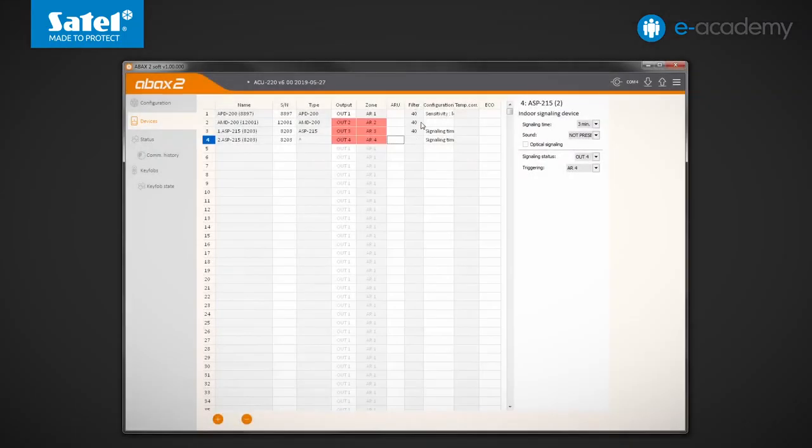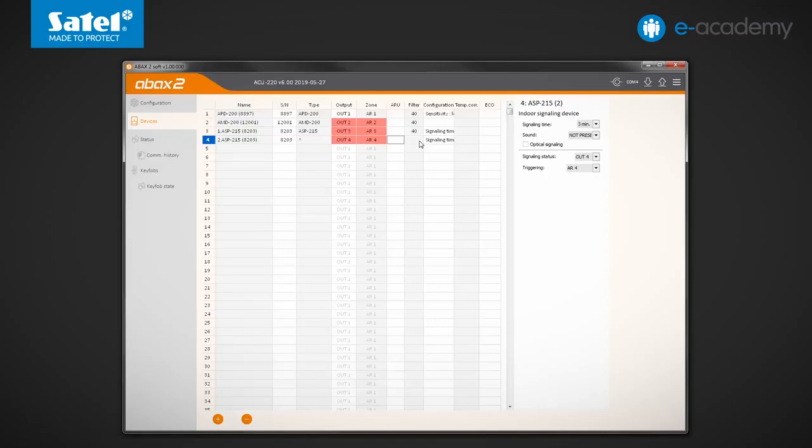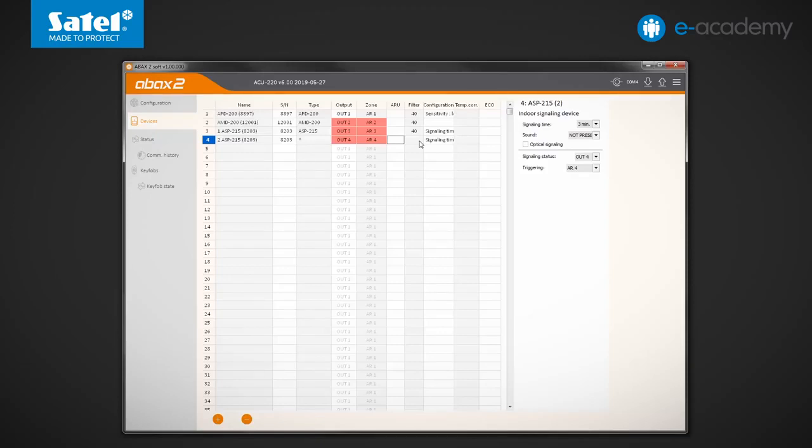The next column is designated filter. It refers to the function of controlling the presence of radio devices in the system. The value entered here defines how many communication periods without contact between the controller and device must pass before loss of communication is reported. If the selected device occupies more than one position on the list, set the filter only for one, the highest position, as it is illustrated by the example of the ASP215 siren.